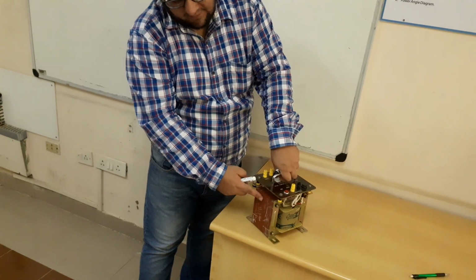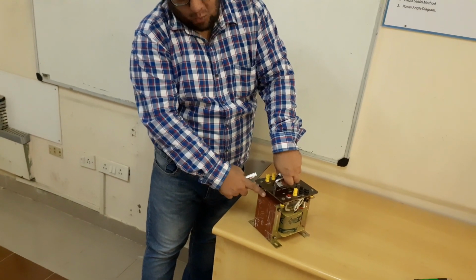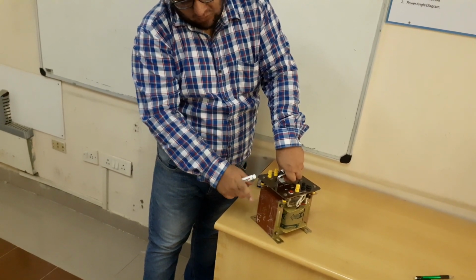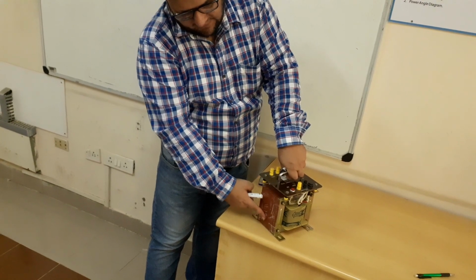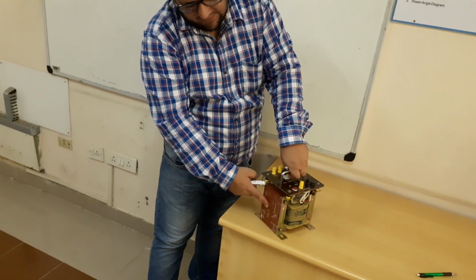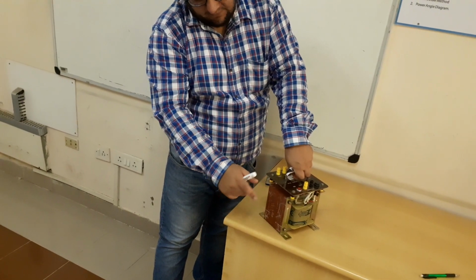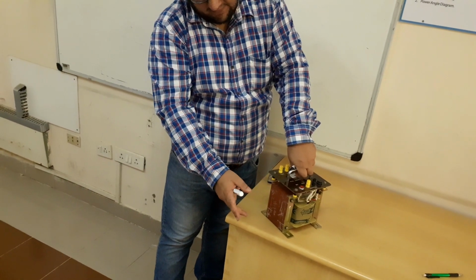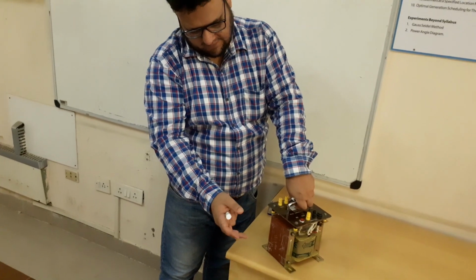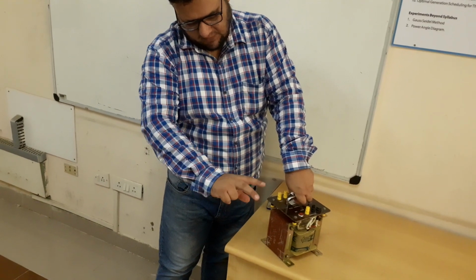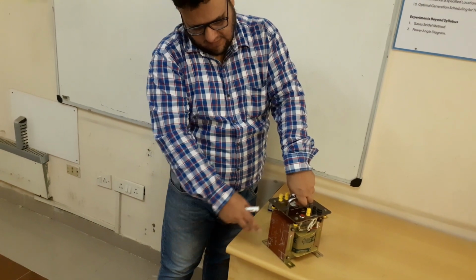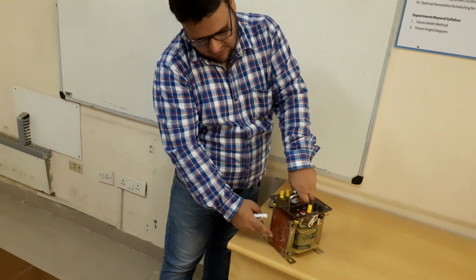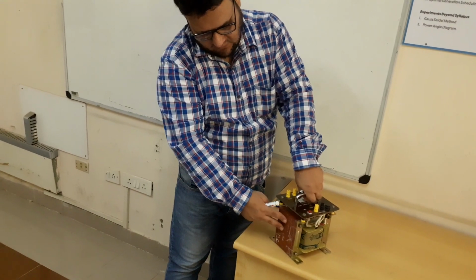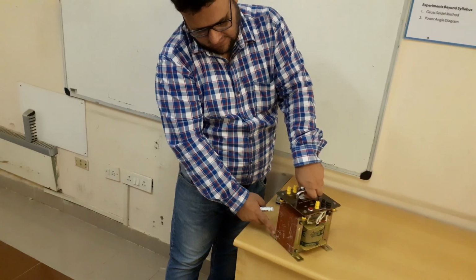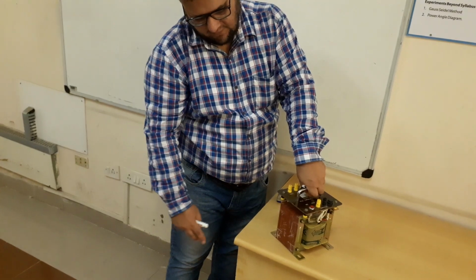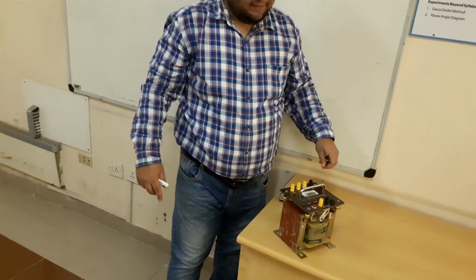So the core losses comprise two components. One is your hysteresis losses. To reduce your hysteresis losses, there is a grading coating of silicon done over here. Whenever you are energizing the transformer, it is getting magnetized, and whenever you are taking the supply off, it is getting demagnetized. That process is called hysteresis. And there are laminations of the surface, so the area for the current flow gets reduced, and hence the eddy current losses are reduced by laminating the core.